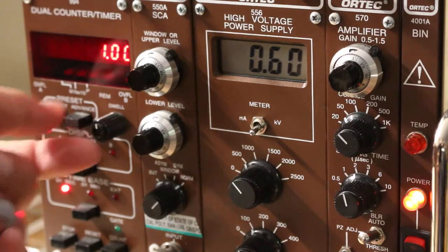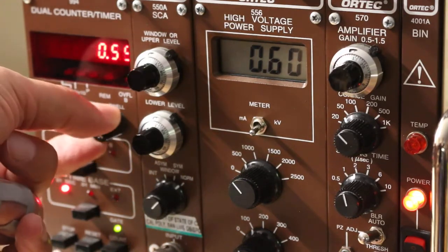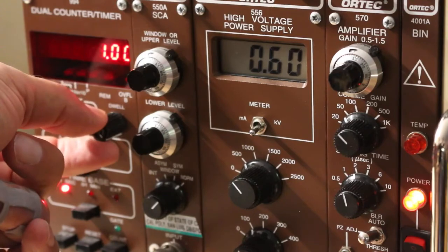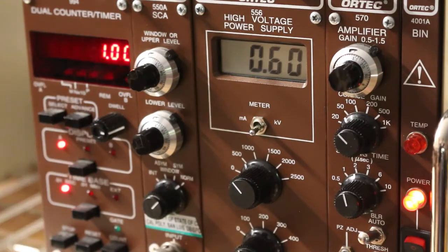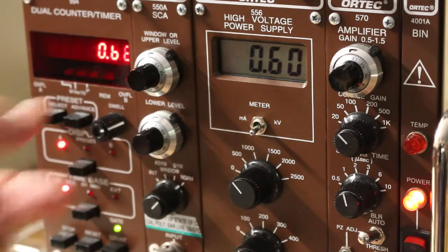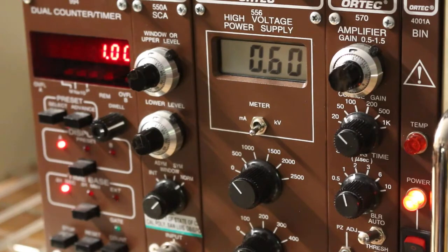And there's a knob here called the dwell time, which you can tell it how much to pause between the time it starts counting again. So see if I turn the dwell time up, you can see that I don't want to wait that much, but see it counts to 1, then it waits for a while, and then it counts again and it waits for a while. If I turn the dwell time up like that, then it'll wait a longer amount of time. And typically the waiting it does is to give you, the operator, a chance to write things down or see what's going on. That's what the dwell time is for.